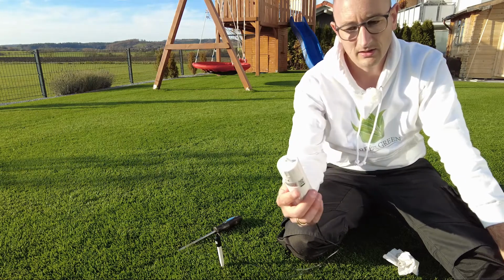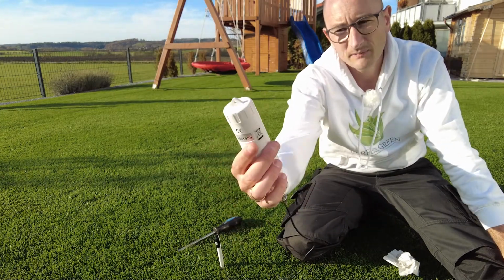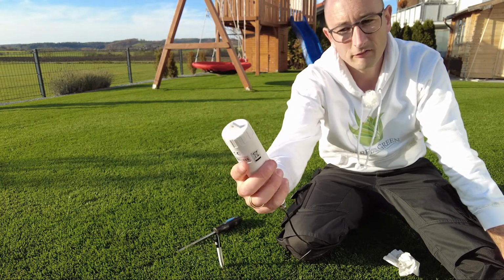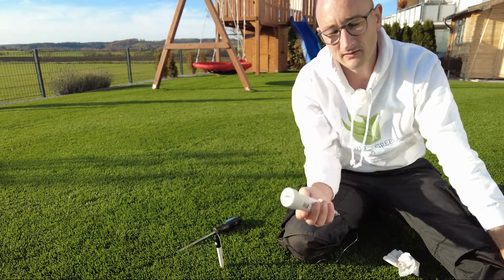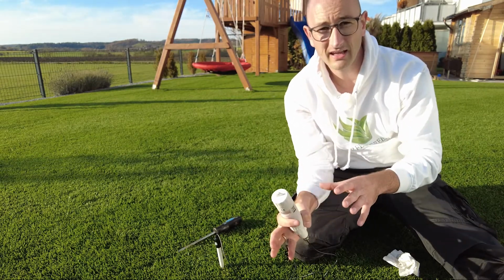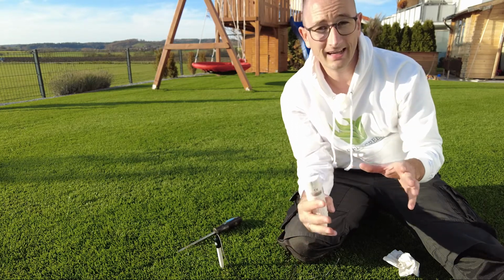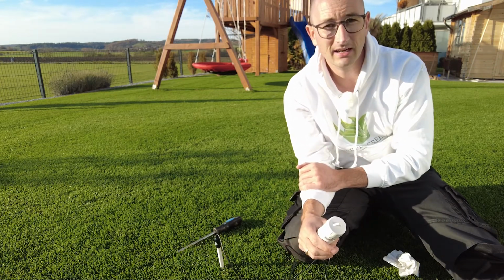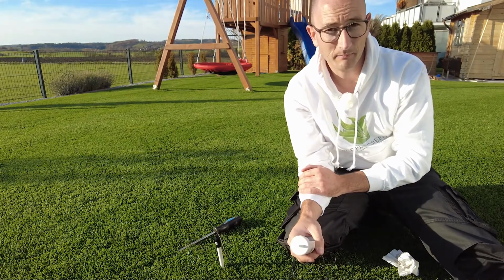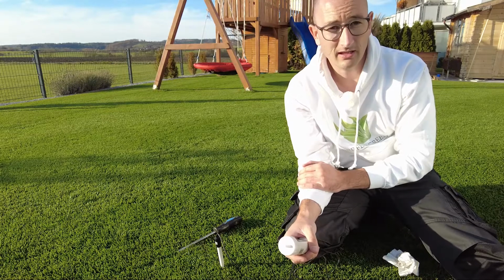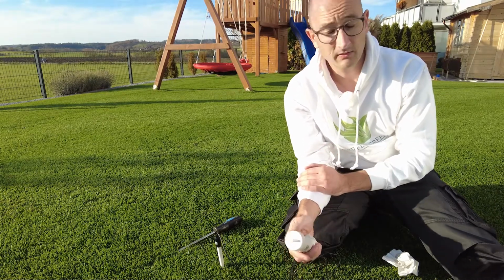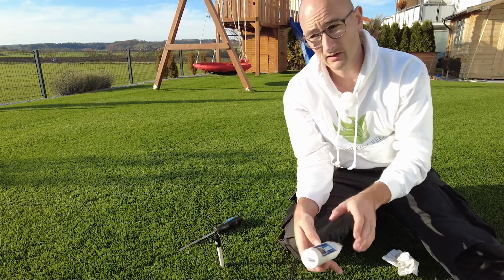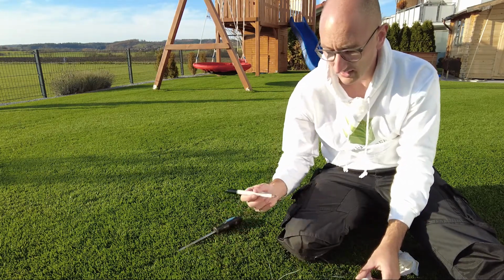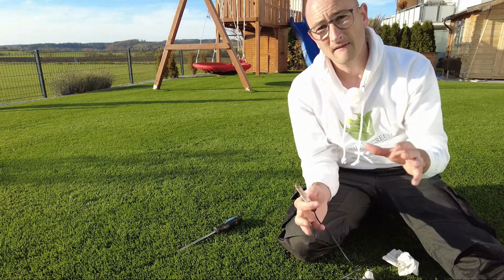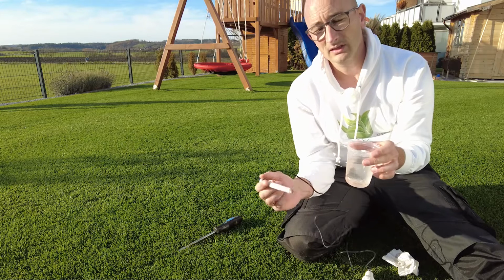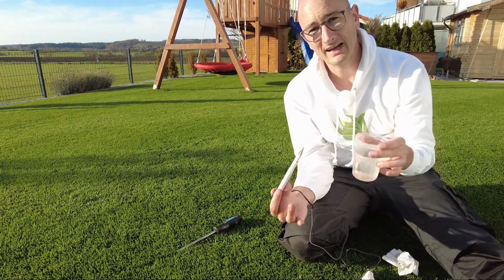And by me it shows a value of 6.97, 6.98, 6.99. It wobbles, it is close to 7. It is a really exact device, and I realize my earth is on the limit. In places it shows a bit less, and you shouldn't have more than 7. I think this device is extremely exact and extremely good, and it is really a super thing. Although it is highly sensitive, because of the glass, you have to be very, very careful. When you want to do another measurement, the producer says to clean it in distilled water.